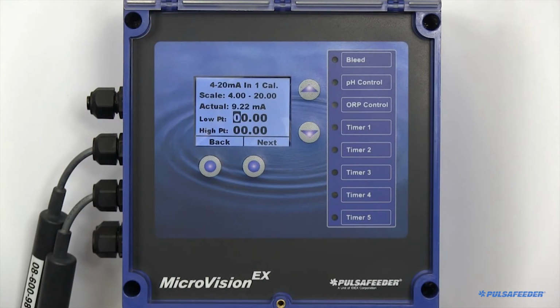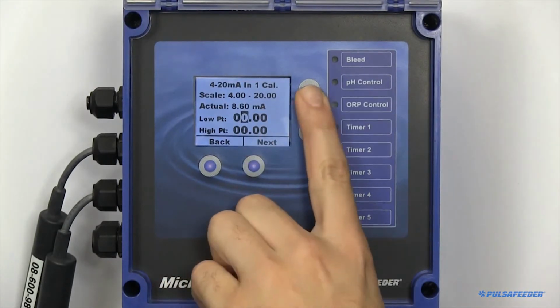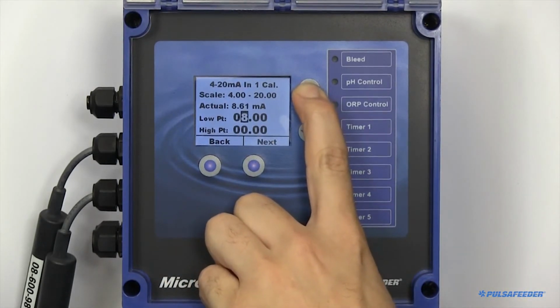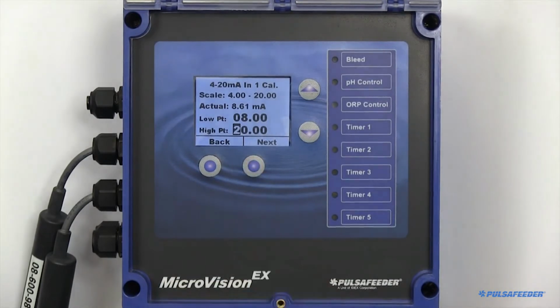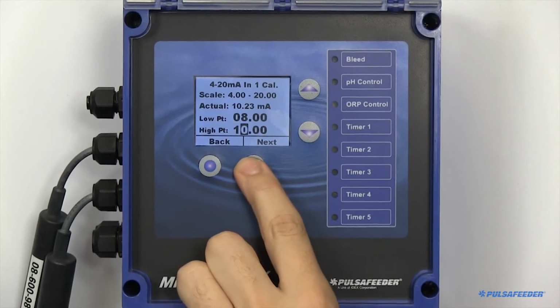Place your probe in its low buffer solution. Wait for the unit to adjust. Enter the correlating value into the controller and enter through just the top row. Next, place your probe in your high buffer solution. Wait for your unit to adjust again. Enter the correlating value and then enter through the bottom row. Your 4 to 20 input board should now be configured.